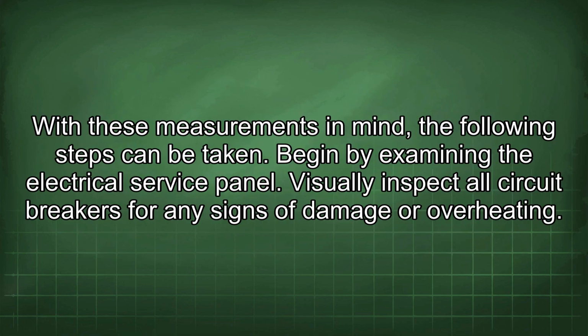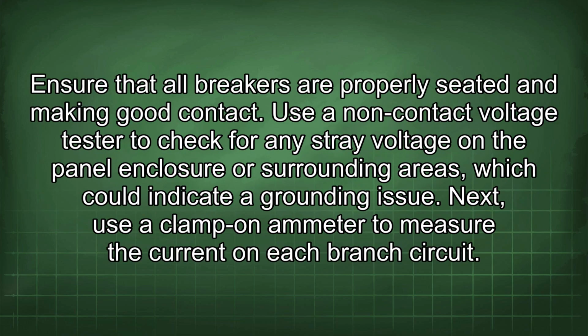With these measurements in mind, the following steps can be taken. Begin by examining the electrical service panel. Visually inspect all circuit breakers for any signs of damage or overheating. Ensure that all breakers are properly seated and making good contact. Use a non-contact voltage tester to check for any stray voltage in the panel enclosure or surrounding areas, which could indicate a grounding issue.